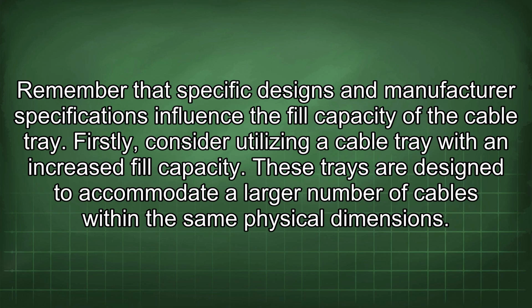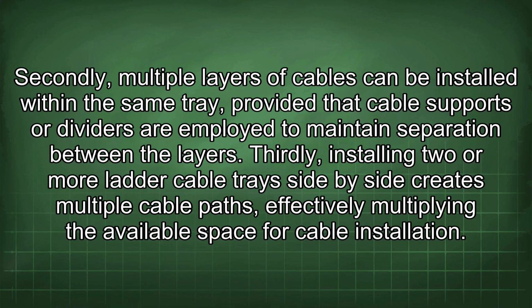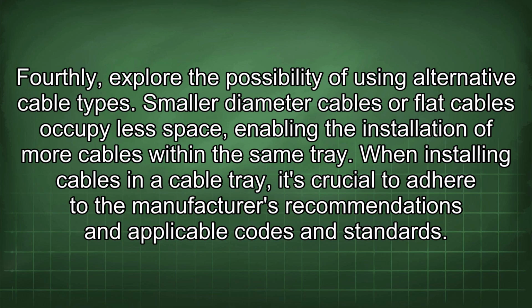Firstly, consider utilizing a cable tray with an increased fill capacity. These trays are designed to accommodate a larger number of cables within the same physical dimensions. Secondly, multiple layers of cables can be installed within the same tray, provided that cable supports or dividers are employed to maintain separation between the layers. Thirdly, installing 2 or more ladder cable trays side by side creates multiple cable paths, effectively multiplying the available space for cable installation. Fourthly, explore the possibility of using alternative cable types. Smaller diameter cables or flat cables occupy less space, enabling the installation of more cables within the same tray.